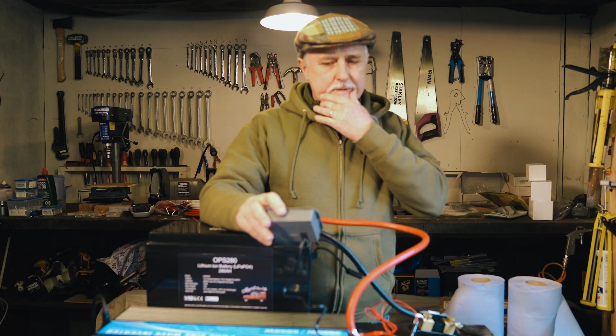We're going to leave this running for about half an hour to an hour. It's drawing around 77 amps at the moment, so that'll be a good test to run for 15 minutes to half an hour. Then we'll stop drawing power and recharge the battery, because it's really important to see what happens when it reaches what it thinks is 0 amp hours drawn - 100% state of charge - and whether it then counts into negative amp hours, which was the problem with the other Junctek shunts. They were pretty useless because of that. Let's let this run for 15 minutes to half an hour and come back to see what it says.